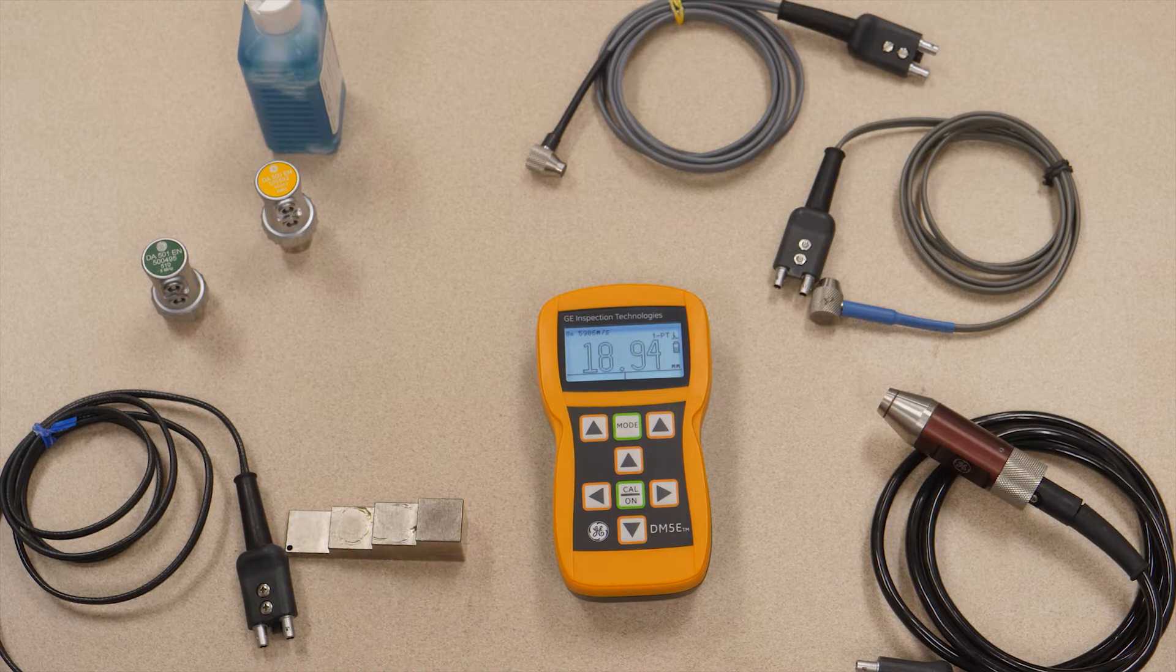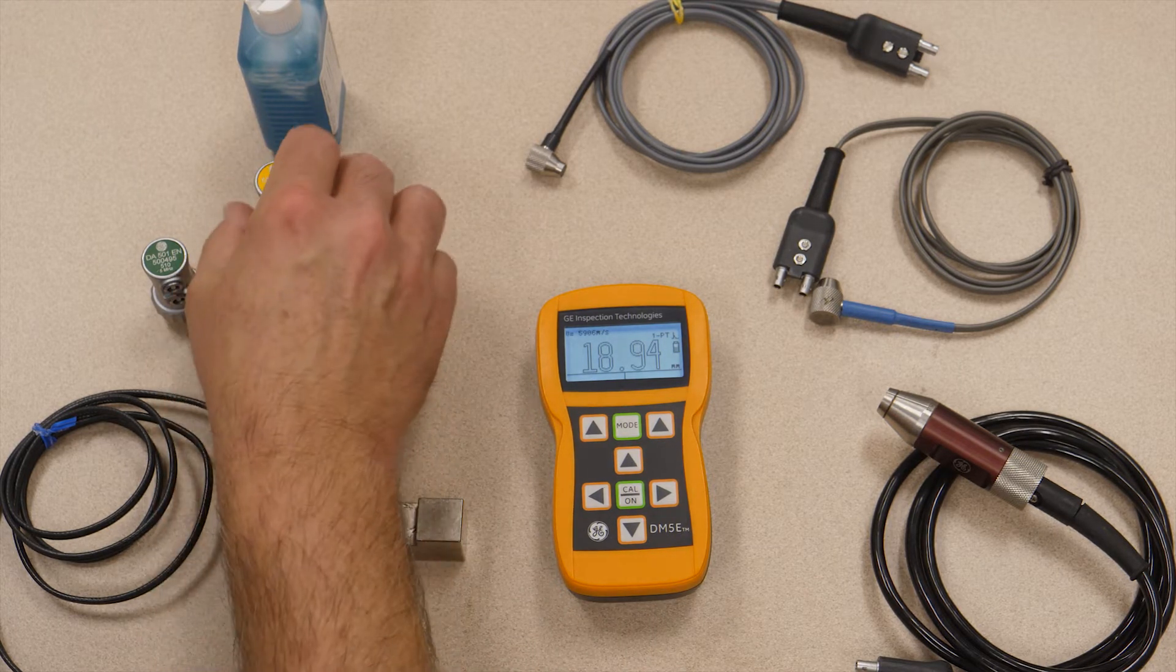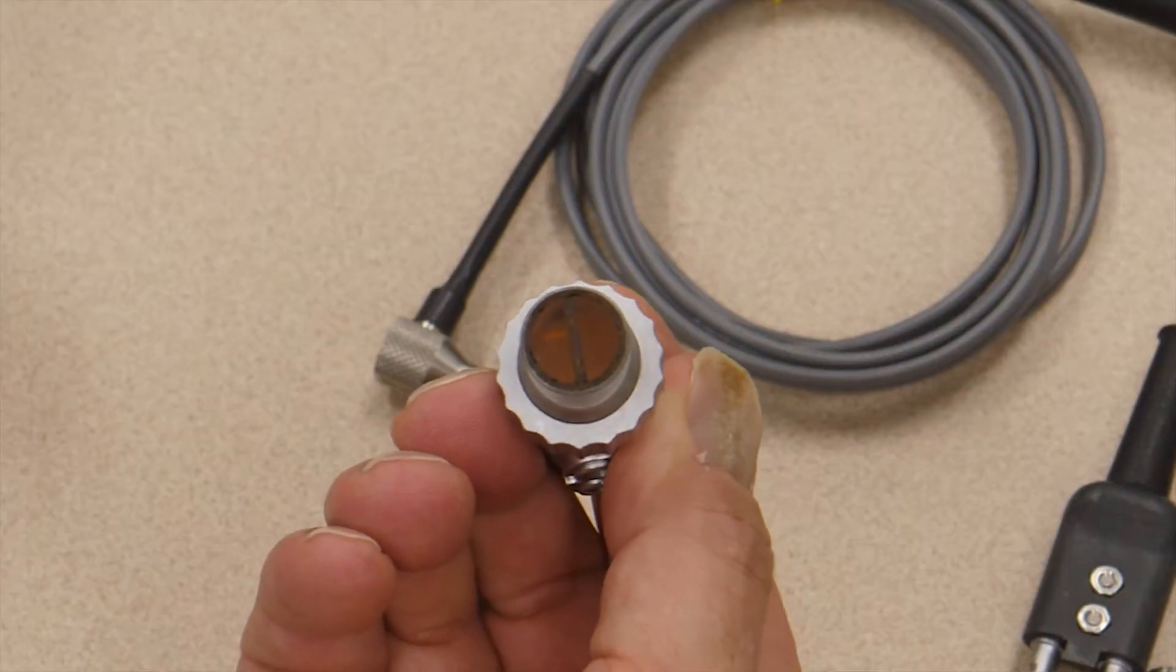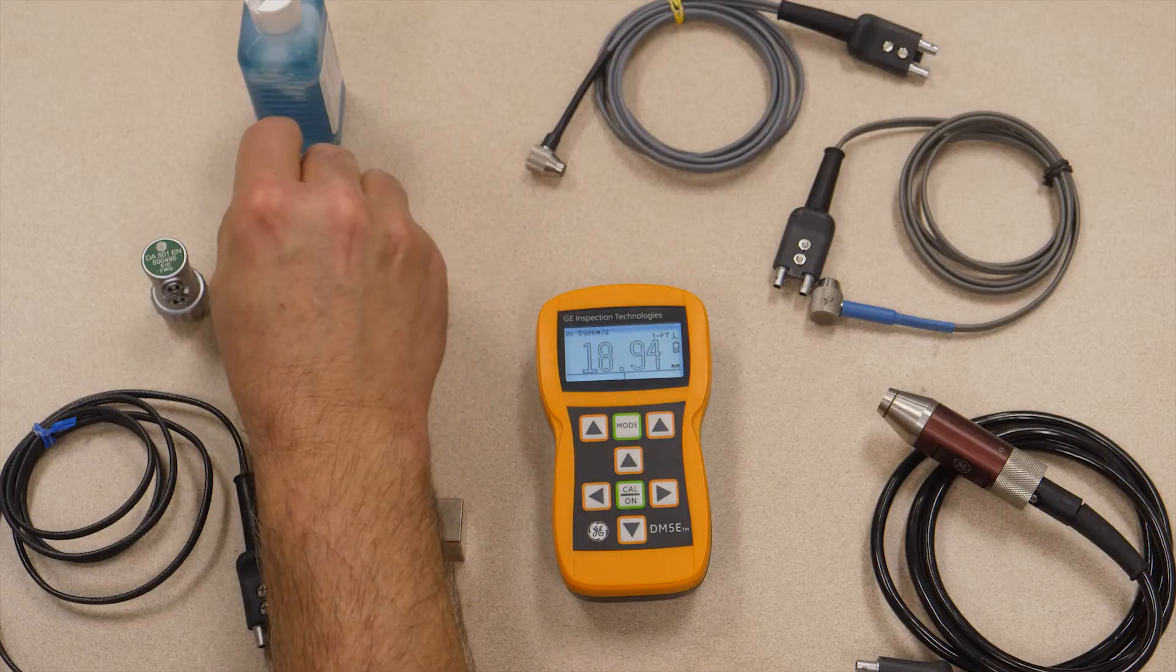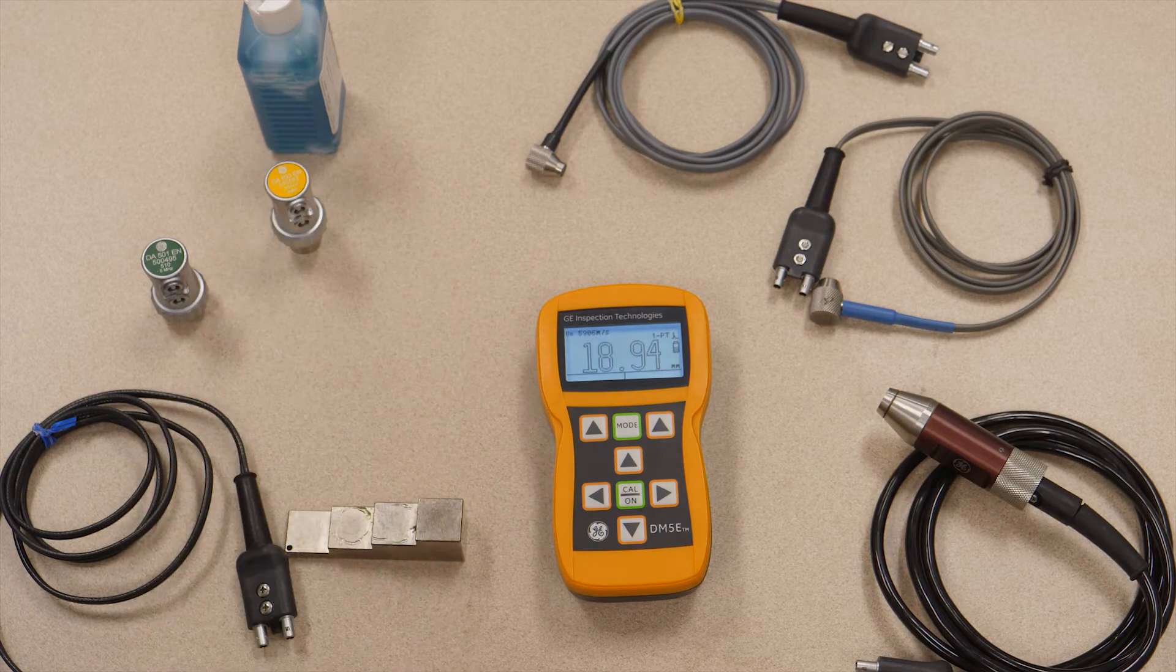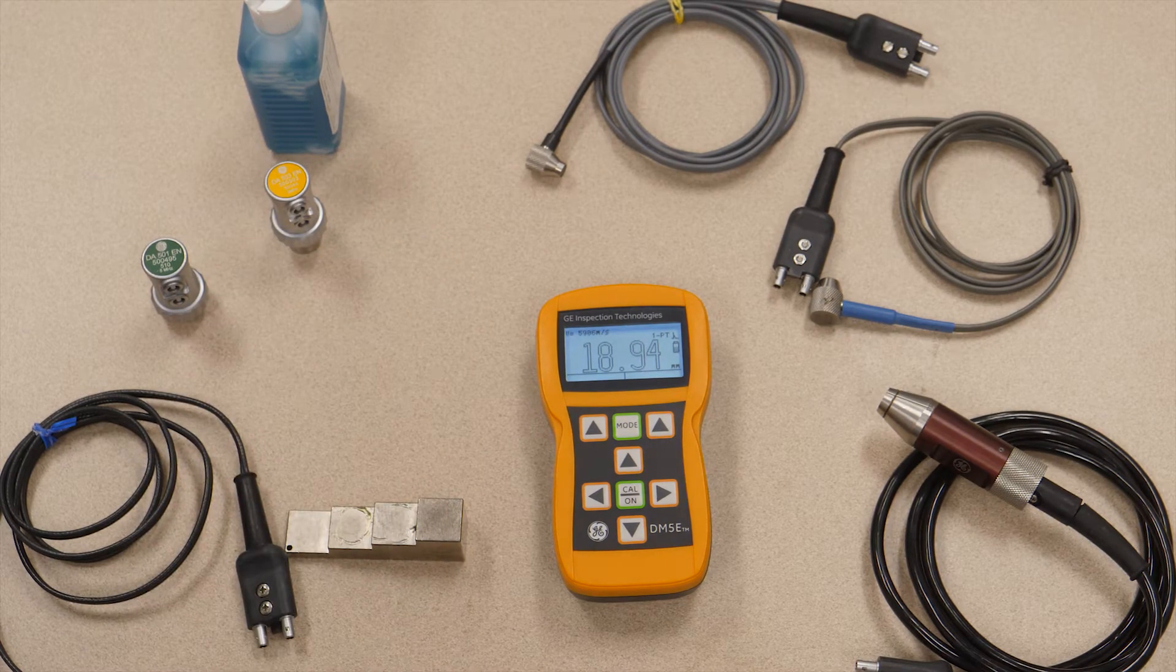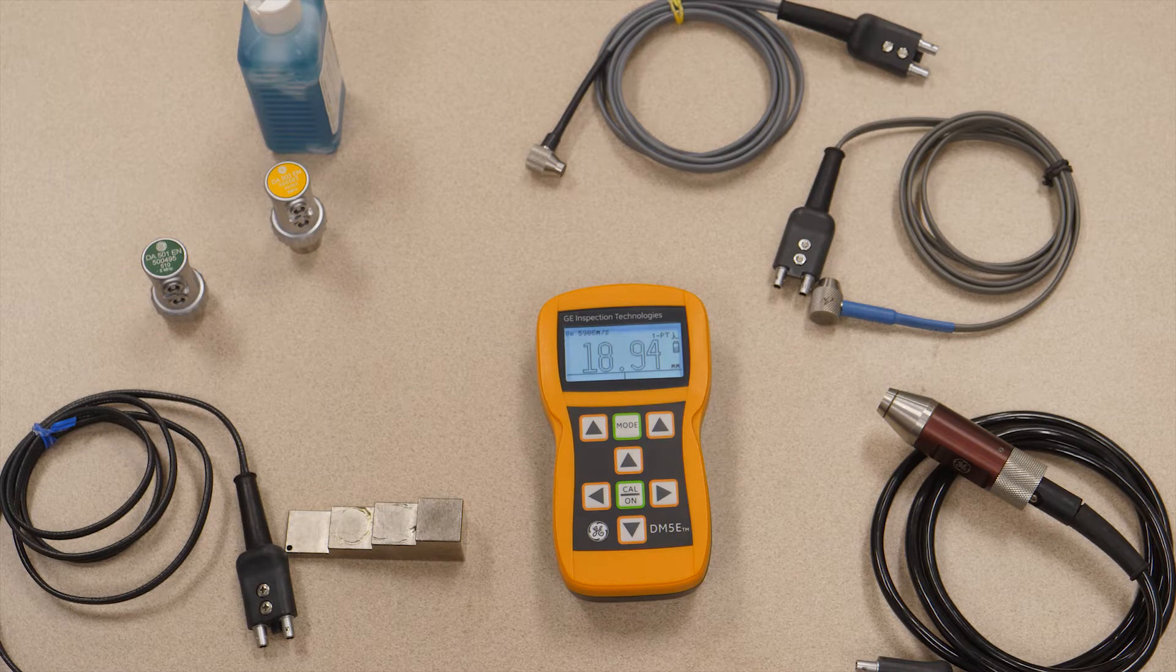This instrument uses only dual element probes. You may be familiar with the dual element probes: pulse on one side, listen on the other, measure the time that it takes the sound to move through the part, and you can turn that into a thickness measurement.